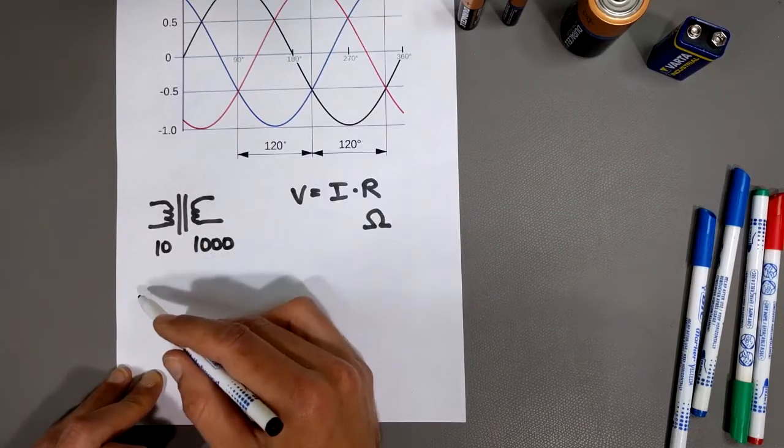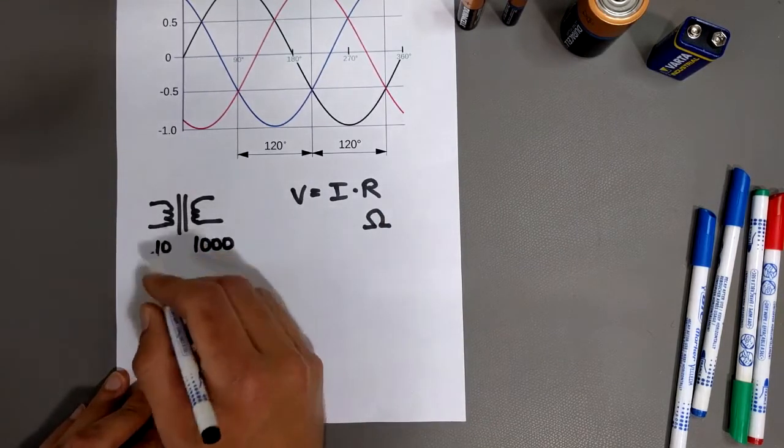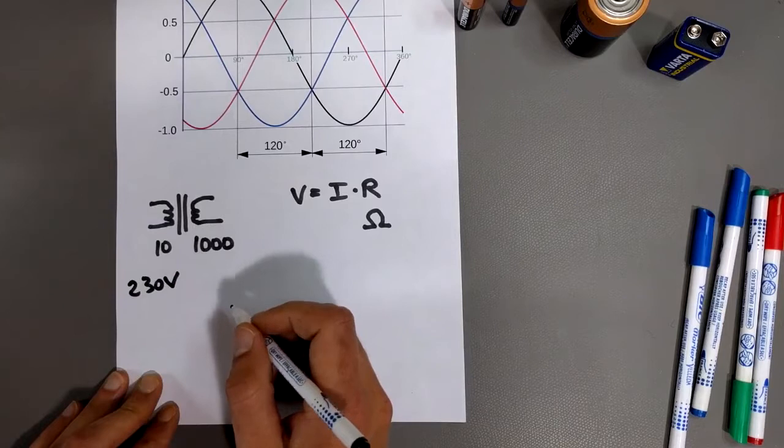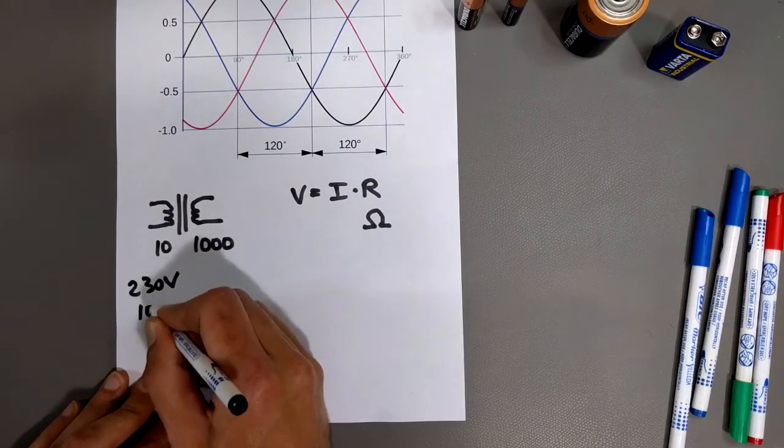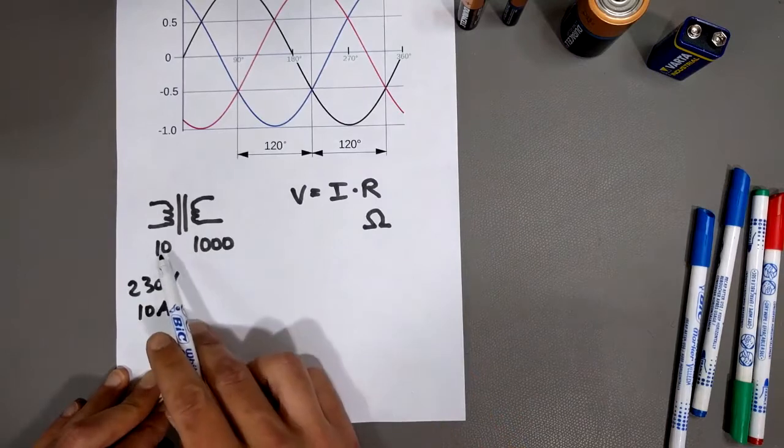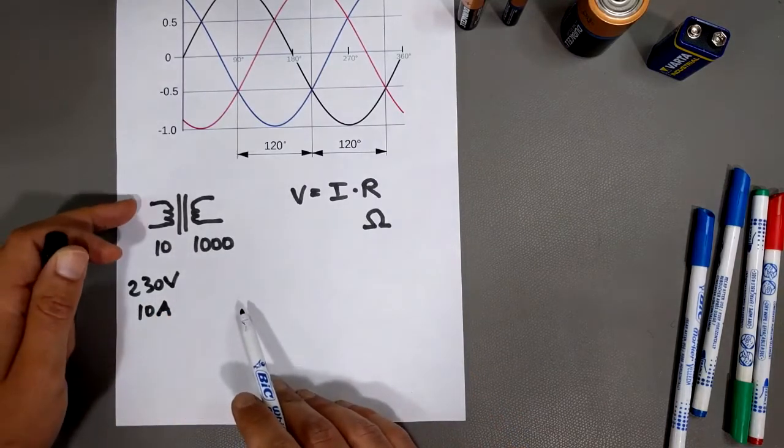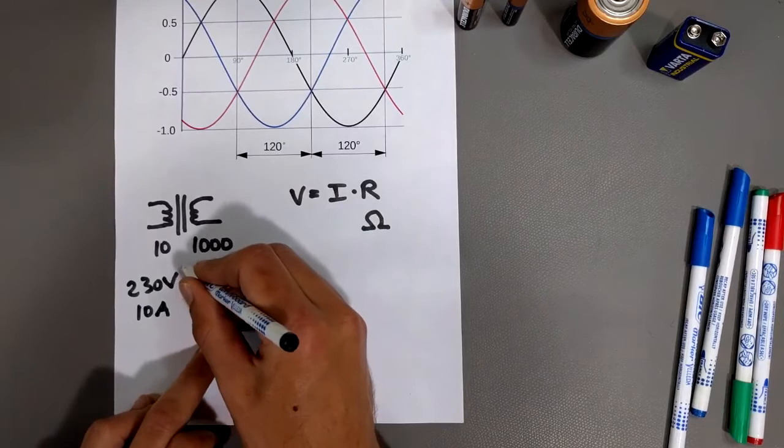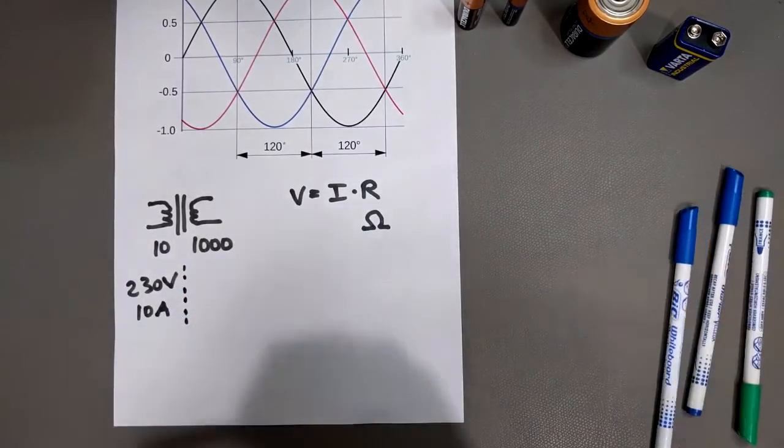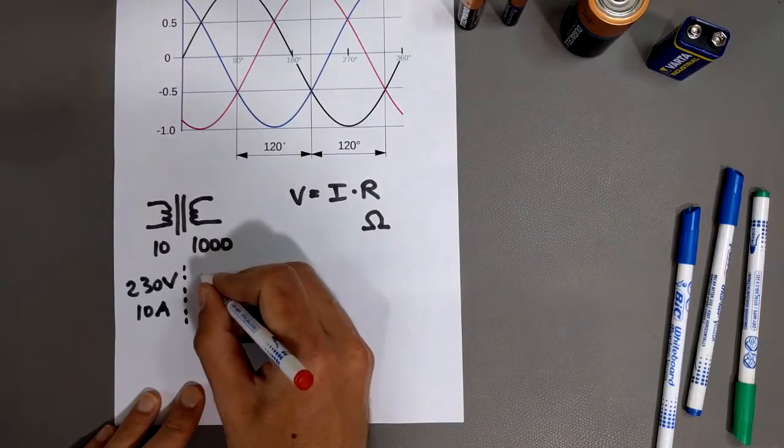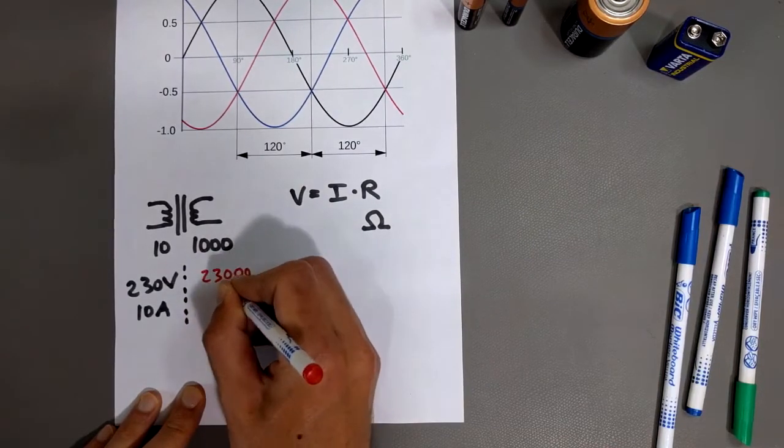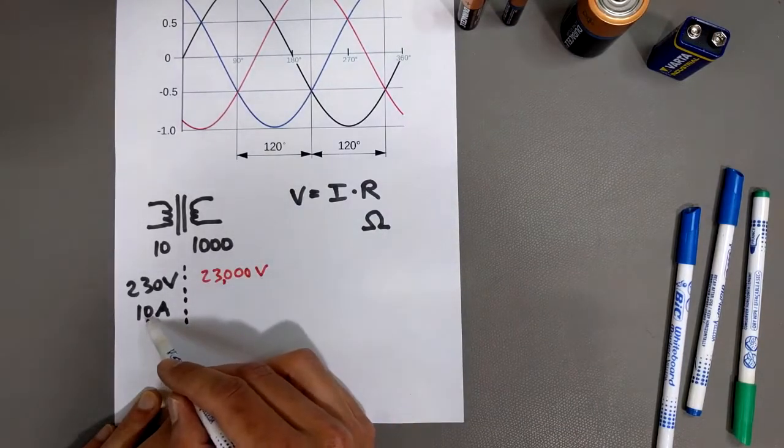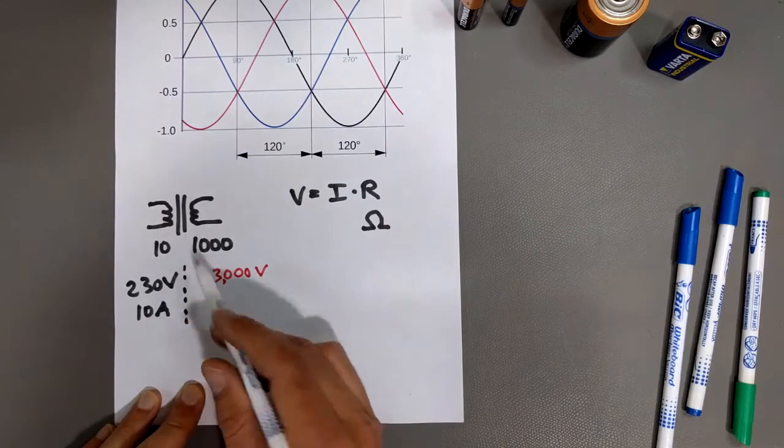let's say we put in 230 volts here at 10 amps. You put 230 volts and 10 amps in here, and at the output of your transformer, you get 100 times as much. So at the output you're going to get 100 times as much, 23,000 volts, but you're going to have 100 times less current. That's the trick of a transformer.